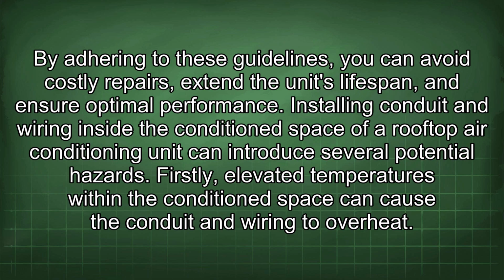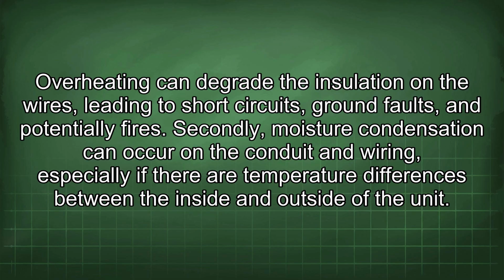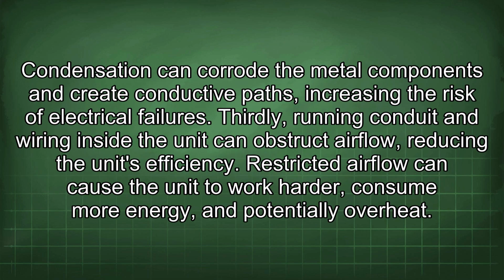Firstly, elevated temperatures within the conditioned space can cause the conduit and wiring to overheat. Overheating can degrade the insulation on the wires, leading to short circuits, ground faults, and potentially fires. Secondly, moisture condensation can occur on the conduit and wiring, especially if there are temperature differences between the inside and outside of the unit. Condensation can corrode the metal components and create conductive paths, increasing the risk of electrical failures.